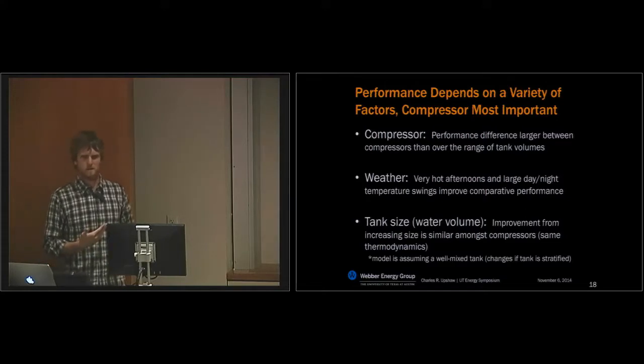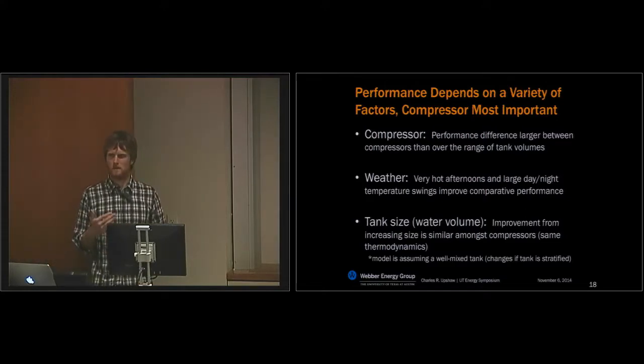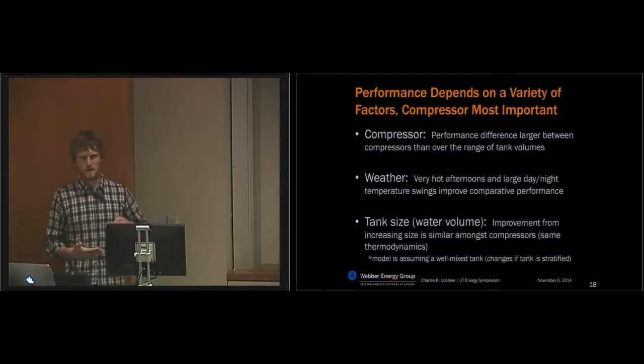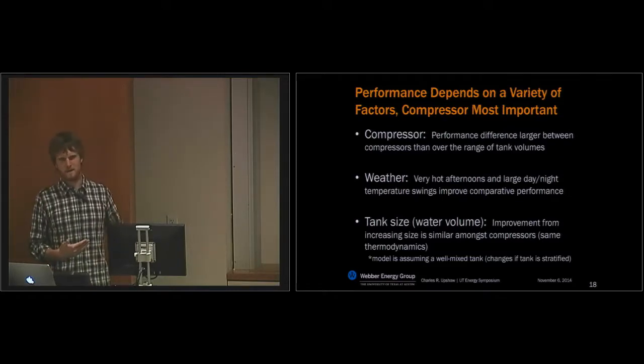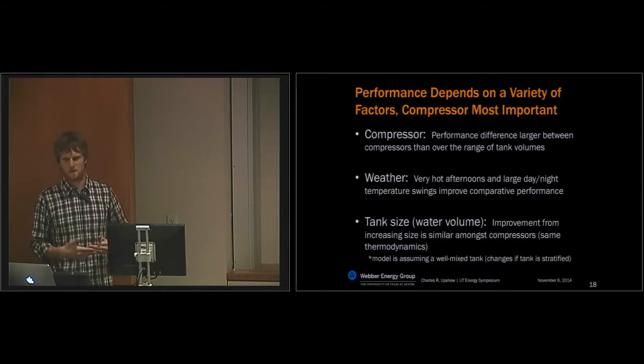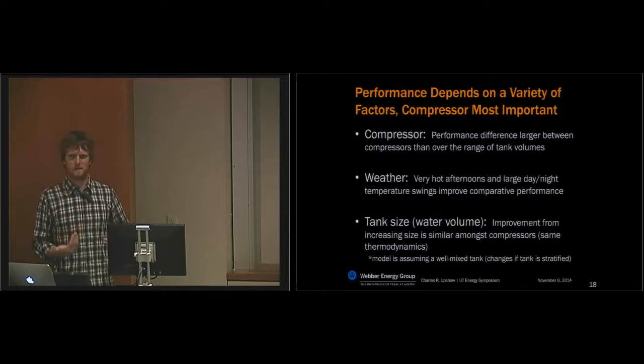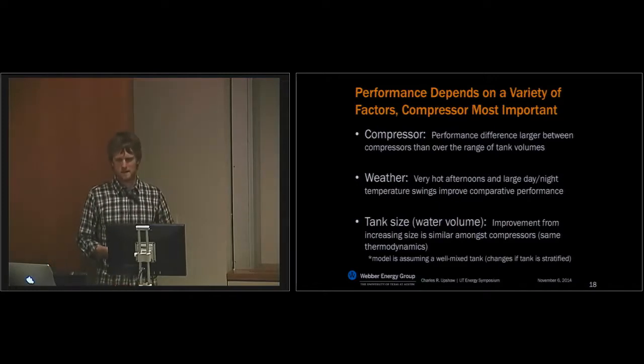It operates best on very hot afternoons and those days where there are very large day-night temperature swings, because the air-cooled condenser operates least efficiently at very high temperatures, and so if you have a mild day, it's not operating that much less efficiently than the water temperature that you're using. And then lastly, the tank size. It is an improvement as you increase in tank size, and this is based on just the same thermodynamics. That's why all of the compressors had roughly the same trend.